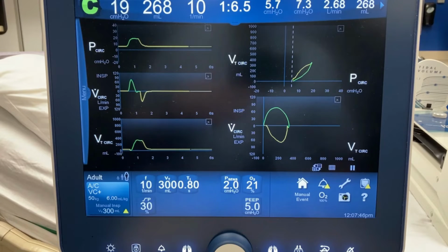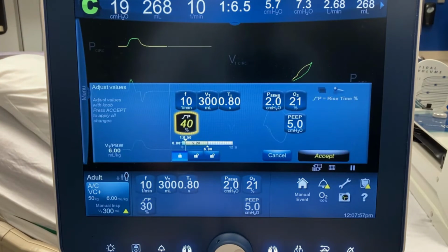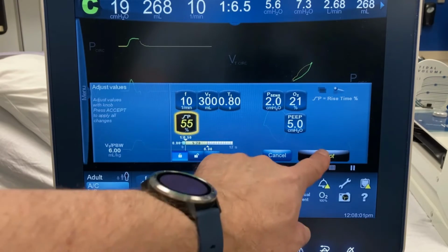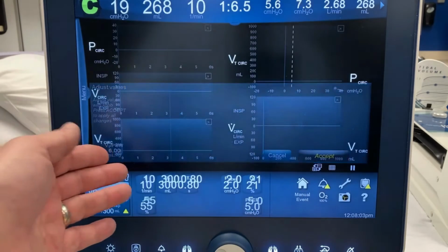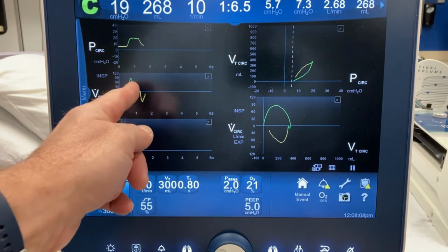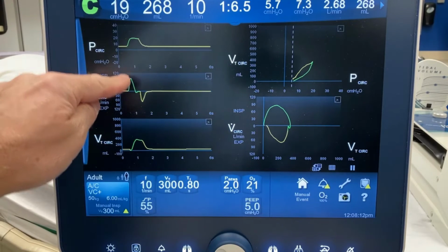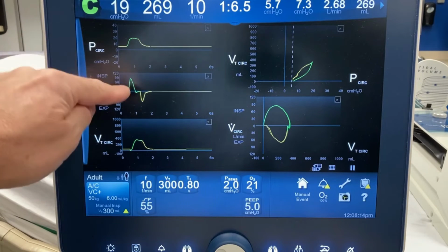You wouldn't think it would make a big difference, but it does. Sometimes patients who are air hungry want to get their flow really fast, in which case on this ventilator, we would set this up. We'd set it to be faster, and that will push the acceleration in faster.